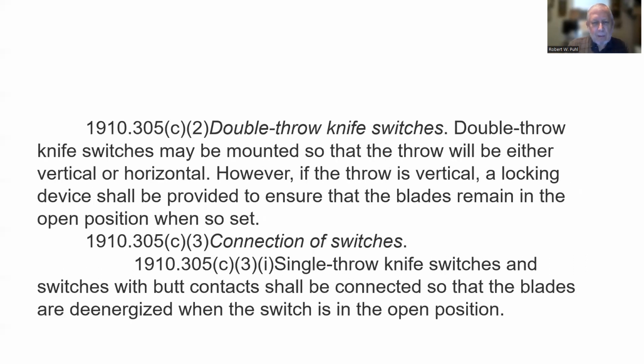Okay. Double throw knife switches, that means they can go either way, may be mounted so that the throw will be either vertical or horizontal. However, if the throw is vertical, a locking device shall be provided to ensure that the blades remain in the open position when so set. Single throw knife switches and switches with butt contact shall be connected so that the blades are de-energized when the switch is in the open position.